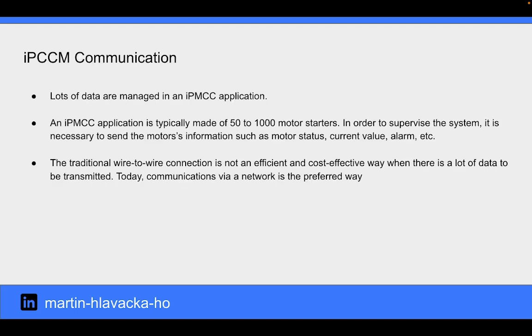Lots of data is managed in an IPMCC application. An IPMCC application is typically made of 50 to 1000 motor starters. To supervise the system, it is necessary to send the motor's information such as motor status, current value, alarm, etc. The traditional wire-to-wire connection is not an efficient and cost-effective way when there is a lot of data to be transmitted. Today, communications via a network is the preferred way.